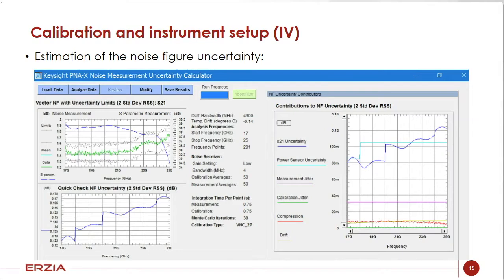Here we have an estimation of the noise figure uncertainty calculated with the software from Keysight, which is running directly on the PNA-X. It takes all the parameters from the setup and also from the DUT performances to calculate the uncertainty we are having in our case. It is running in real time, so we can see the changes and the effect of different parameters. We have the overall uncertainty on the bottom, and on the right side, we have the different contributions to our uncertainty. This is a general example. We will see a specific example later.